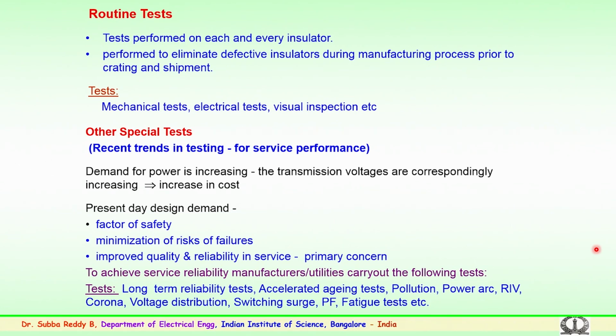It has to be maintained, else without proper voltage distribution, the insulator which is near the line end sees very high voltage across it, very high stress, and over a period of time the insulator could shatter and could lose its insulating properties. That is the reason a proper voltage distribution has to be maintained for the insulator string with proper corona control rings, arcing horns, or suitable hardware which is being employed for the string.